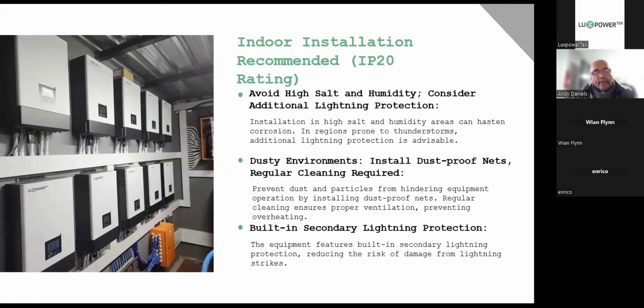A good installer will include the surge protection device on both the DC and the AC side of his installation, because you're protecting the customer's investment. We do have lightning protection inside the machine, but not in the form of an SPD. These are metal oxide varistors. And we have 5 of them inside there on each input. So we do our best to protect the machine, but that's not the last bastion of support.